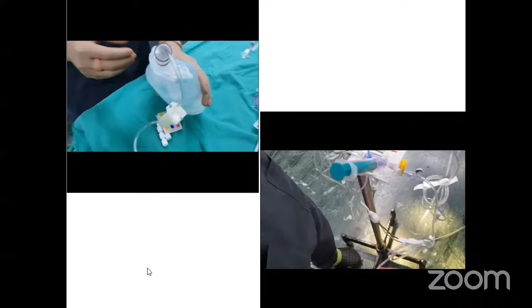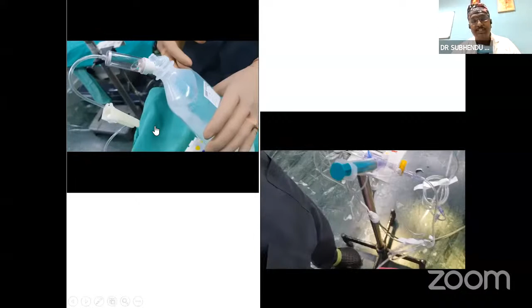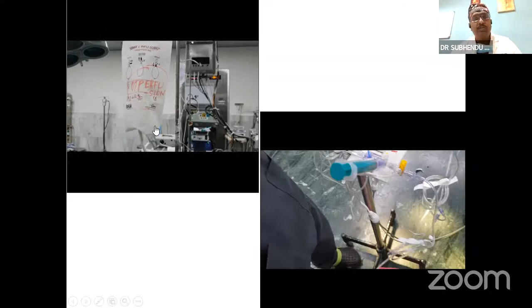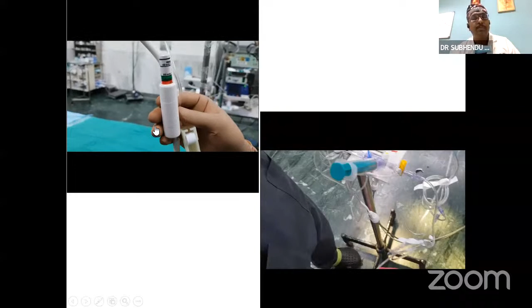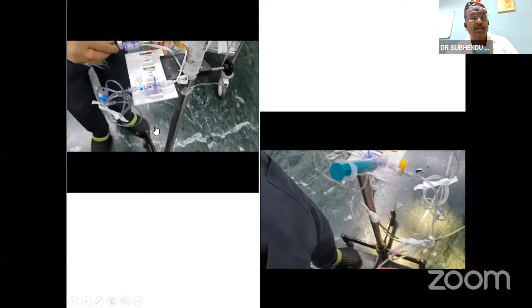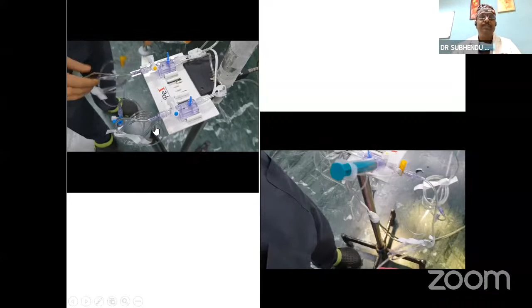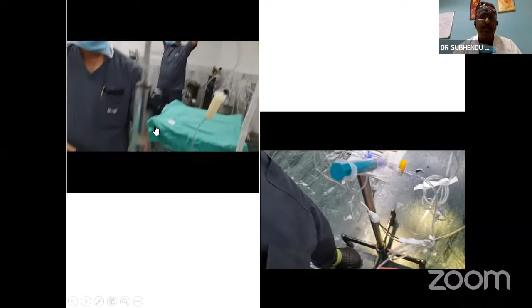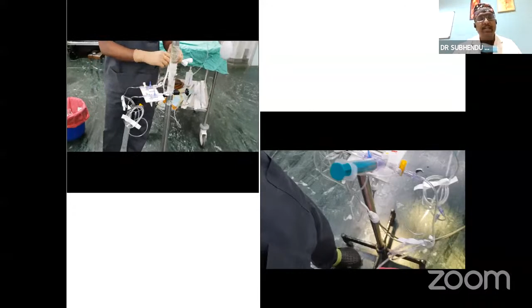The video is seen. So in this video, where my pointer is, I am describing the three systems: the transducer system, the flush system, and the coupling system. Now what I am showing is how we prepare the heparinized flush system. We can start giving pressure to the bag and see the amount of pressure, which is near about 200. You can see the color code, the green zone. The entire flush system is being prepared. The yellow one is the arterial connection and blue is the venous system. We can connect a central venous catheter or a pulmonary artery catheter. This is the transducer system, and this is the coupling system.